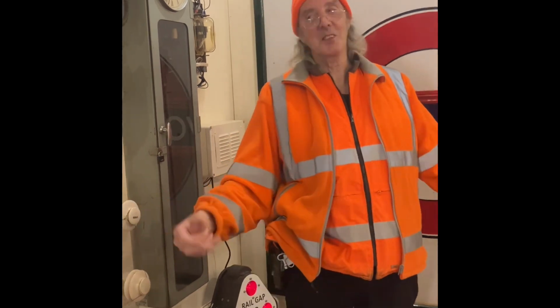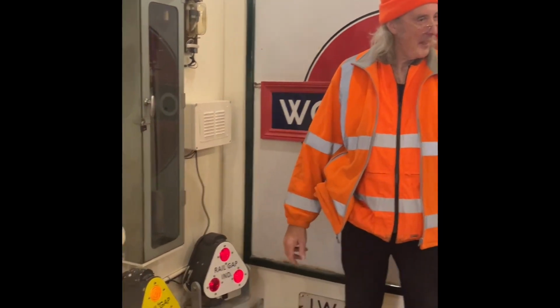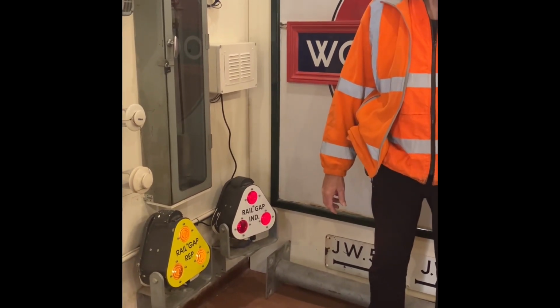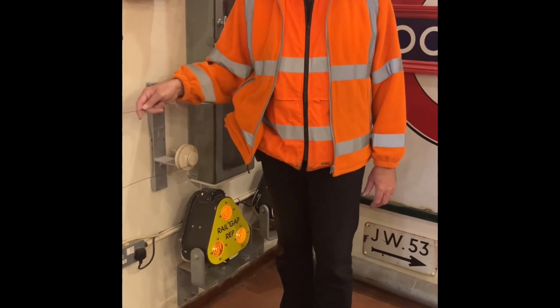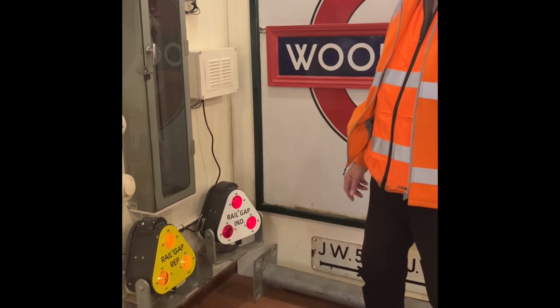The tunnel ones now are meant to be insulated and the heavy equipment still works. These are still there, but they never clean them anymore, so they're as dirty as the rest of the tunnel. Yeah, very conductive. I went to an incident where they corroded off the wall with a big water ingress. They corroded off it. It was all over the track. Oh my word. Yeah, it's only low volts, they're only about 5 volts, so, you know, put 630 volt current through, that probably hurt at the other end.